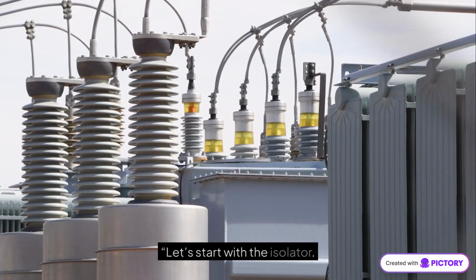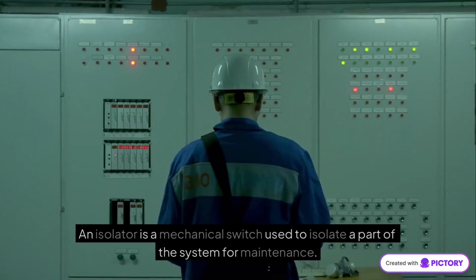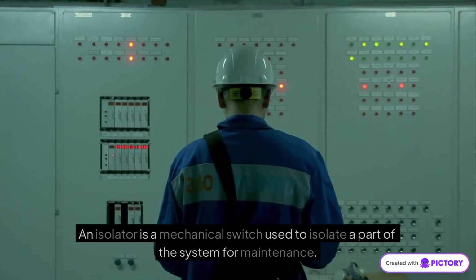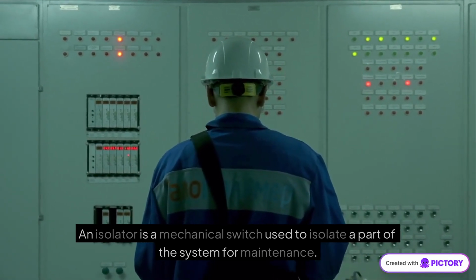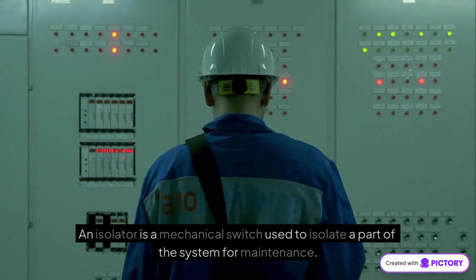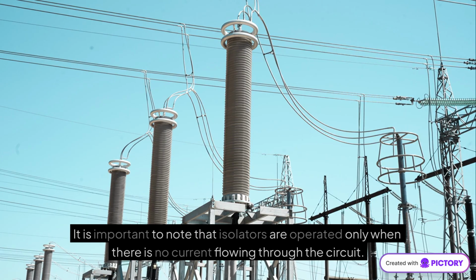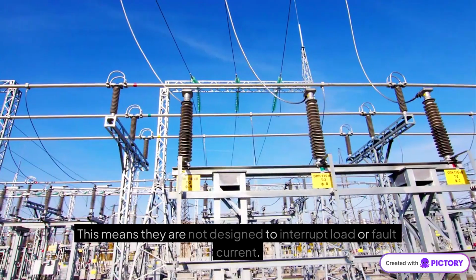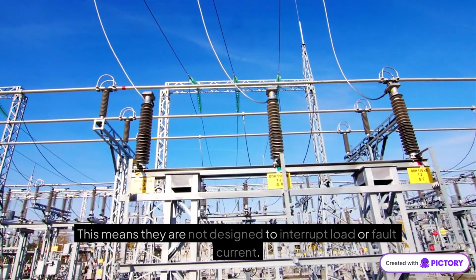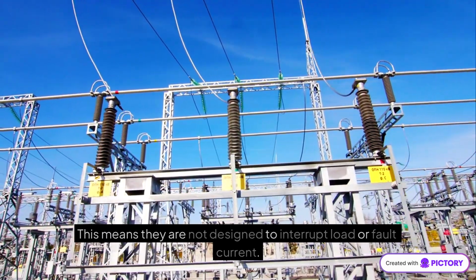Let's start with the isolator. An isolator is a mechanical switch used to isolate a part of the system for maintenance. It is important to note that isolators are operated only when there is no current flowing through the circuit. This means they are not designed to interrupt load or fault current.